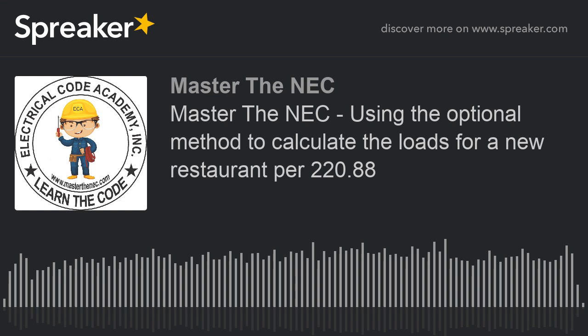Again, if it's a 120/240 volt restaurant, then I'm just going to take that kVA and divide it by 240, and then that's going to tell me what my service needs to be. That's going to help me size my conductors. Okay, you get it? So a lot of people get this confused.